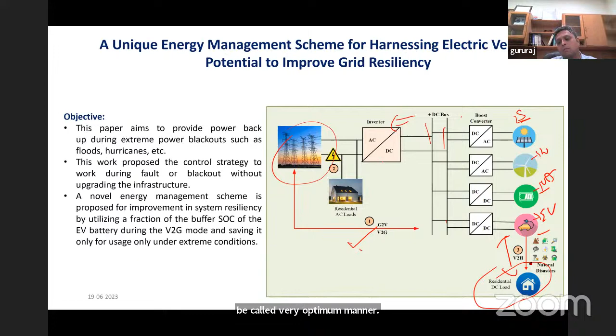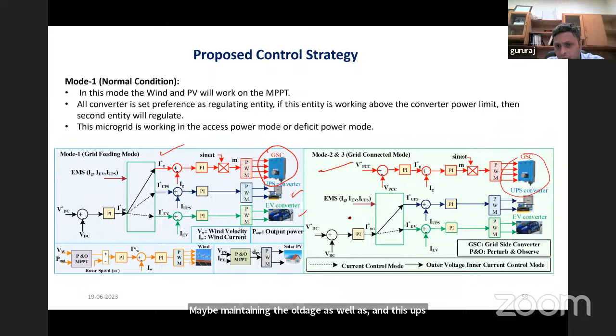This is the proposed control strategy during grid feeding mode. The grid side converter, the three-phase inverter, would be exchanging power with the grid, and the UPS converter and EV converter would be in charging mode. During mode 2 and 3, the grid connected mode, it behaves in an isolated manner as well. What happens is the grid side converter may maintain the voltage, and the UPS converter or EV converter may maintain the voltage during isolated operation.